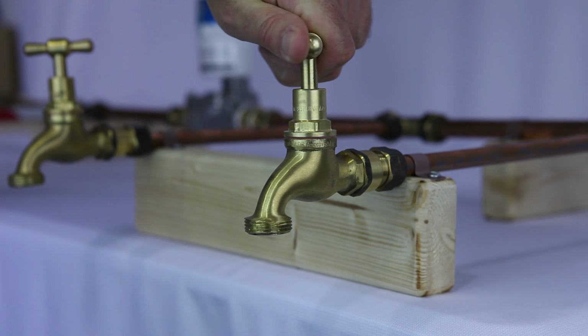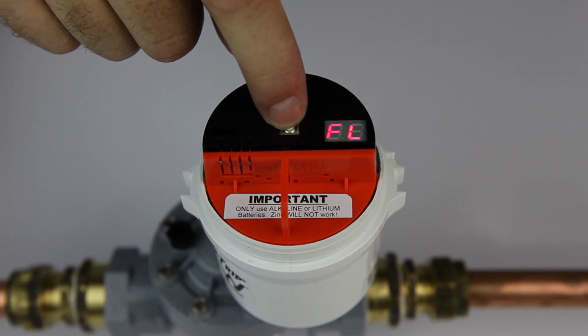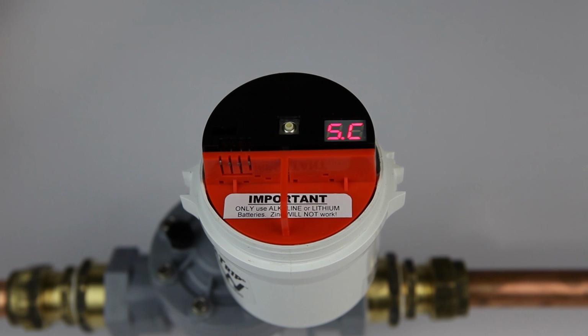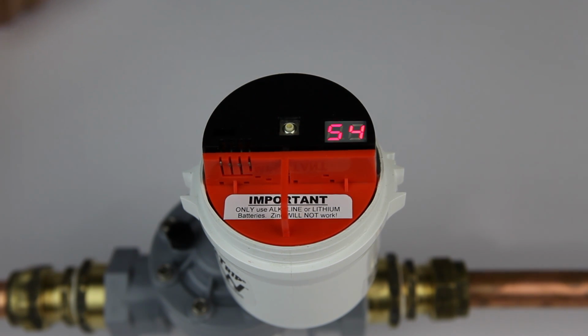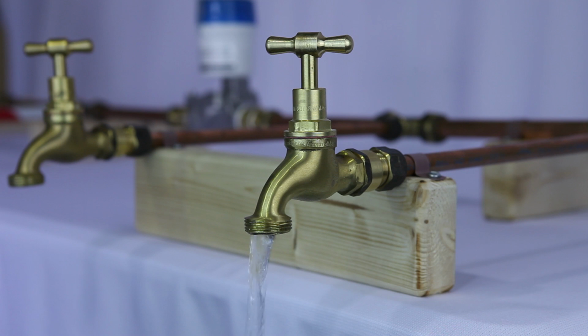Next, we're going to do the water shut-off test. Turn the tap on again. Then press and hold down the button. First, FL for flow will appear to let you know the sensor can see the flow. Hold the button down until system check is displayed. Then immediately release the button. The display will switch from SC to a 60-second countdown timer. Once the counter reaches 0, the water will shut off. At 0, the display will go out and the control unit will trip the shutoff valve and shut off the water. This checks that the shutoff valve is working correctly.